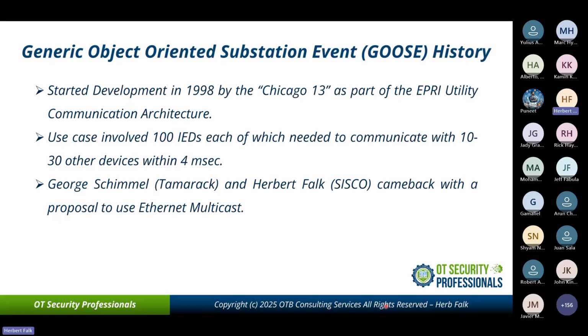So the generic object-oriented substation event, GOOSE, started in 1998 by 13 of us as part of the EPRI utility communication architecture. The use case that GOOSE ended up being designed for was a large substation with 100 IEDs, each of which needed to communicate with 10 to 30 other devices within 4 milliseconds because of an event, a tornado basically coming through the substation.